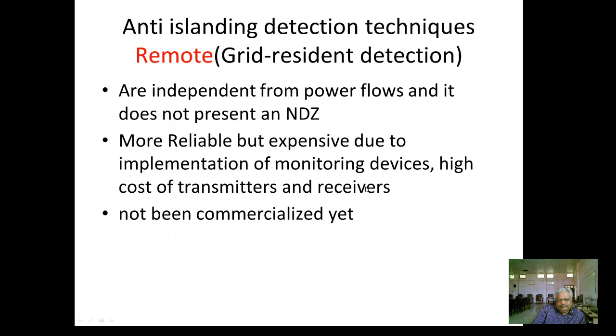Now, what is the next method of remote grid-resident detection? You have again distributed generation on this side, grid on this side. Now when the circuit breaker opens, what will happen? It will get automatically connected to this capacitor bank. And this connection of a circuit breaker to the capacitor bank brings this capacitor in parallel with the distributed generation. That causes a large enough voltage change to trip the over and under voltage protection on this side, because switching of a capacitor causes a high voltage on this side.